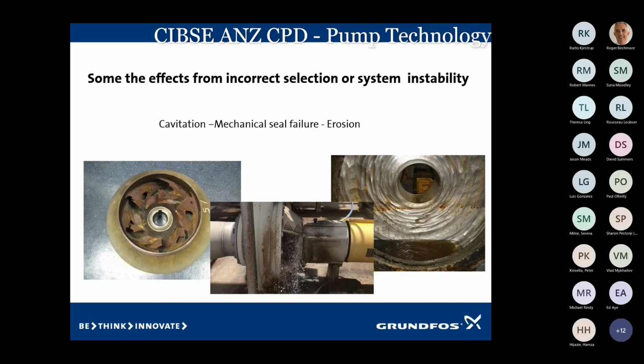The one on the right is the back end of a pump housing. There's a lot of erosion going on there, and you will see that if the pump is running at its best efficiency point, and then all of a sudden it shifts out to the right-hand end of the curve. A typical case of that would be a swimming pool. You're running the pump, which is circulating water around the pool, and then you flick it over to a backflush, and under a backflush, the head's different. The head's a lot lower, and all of a sudden the pump will just shift straight off the end of the curve. Now that pump housing is probably 10 mils, 12 mils thick, and I've actually seen jets of water coming up the back of some pump housings caused by erosion.